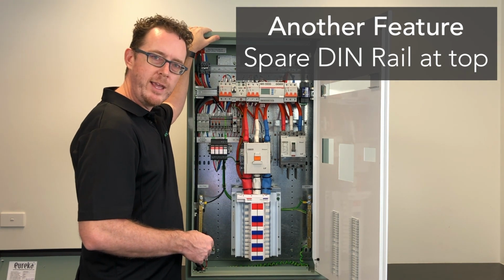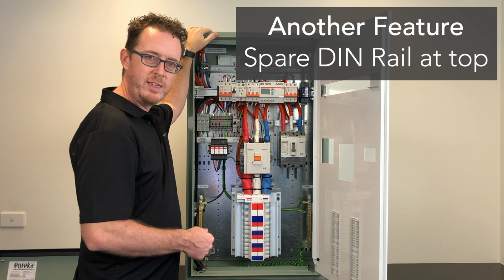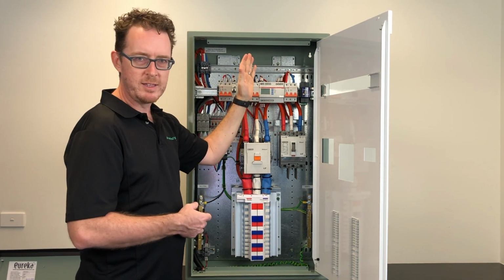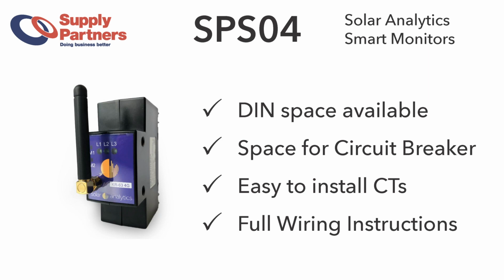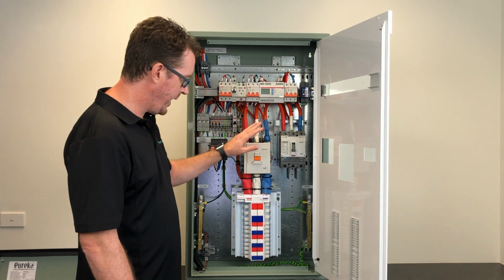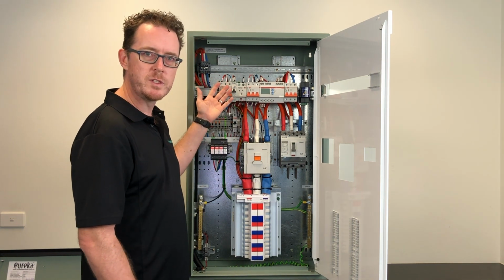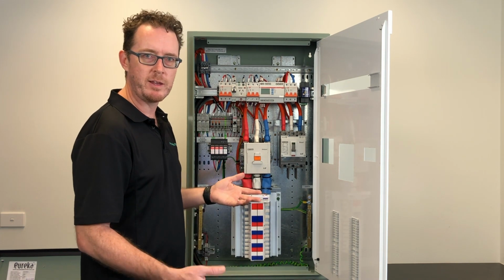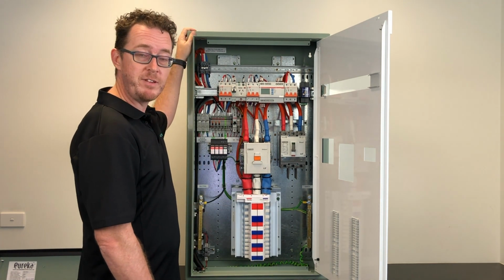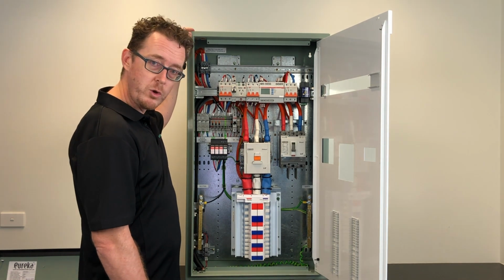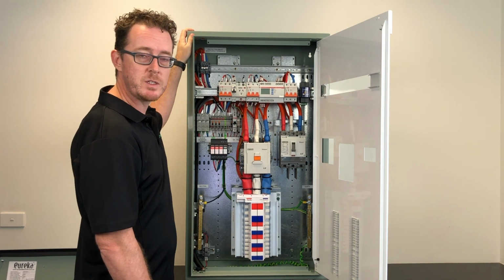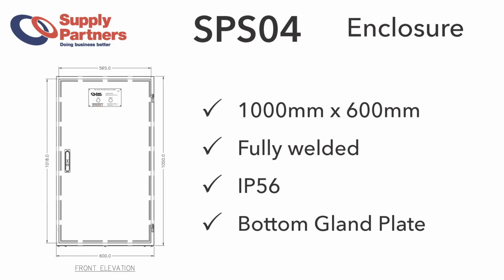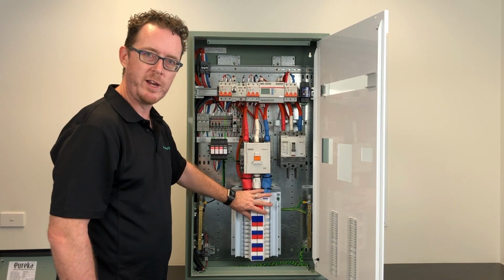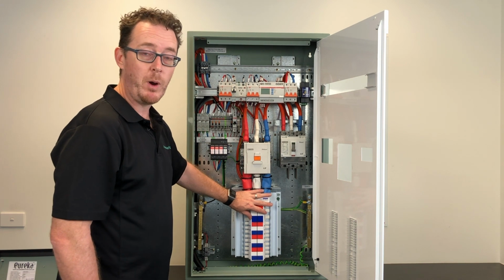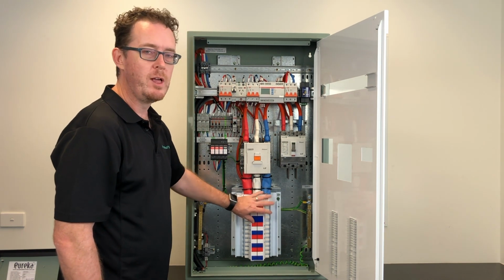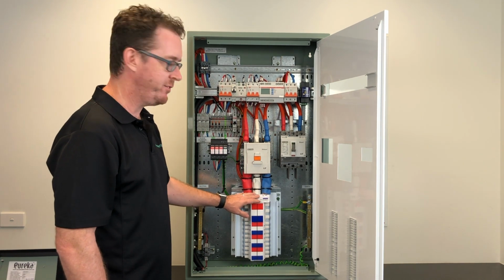We will be offering a range of options for the board, the surge protector being one, solar analytics being another. There are spaces set up for the CTs to go straight away, and you can also get things like rain hoods and mounting brackets and things of that nature for the enclosure as well. The enclosure itself is IP56. It is a full welded enclosure, high quality enclosure. This is going to last for years in any environment, whether that be inside, outside, etc. We will also be offering the SPS04 in a variant whereby we don't build in the distribution chassis at all, and we allow for the direct connection of an inverter to the contactor.